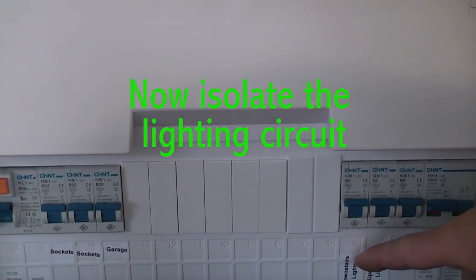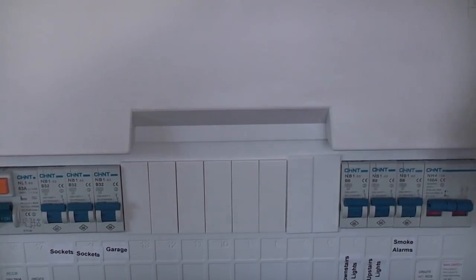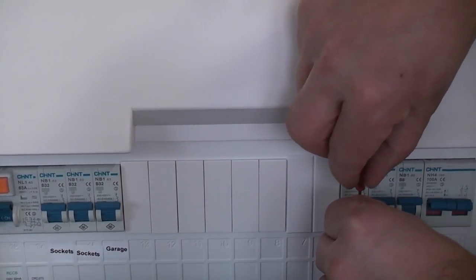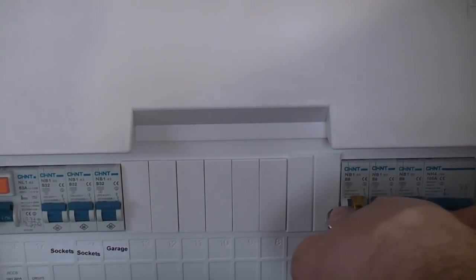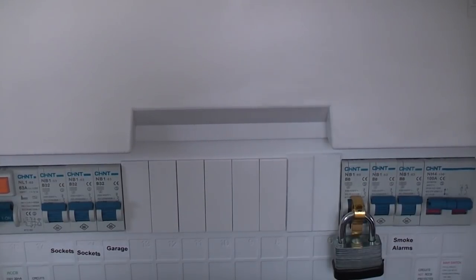This is the consumer unit. You can see the downstairs lights are clearly identified, but you should never take it for granted that a switch isolates the entire circuit — you always need to check. We're going to isolate that switch and then lock off the MCB using a lock-off device, putting a padlock through it so there is no chance of anybody switching that circuit back on while we are working.